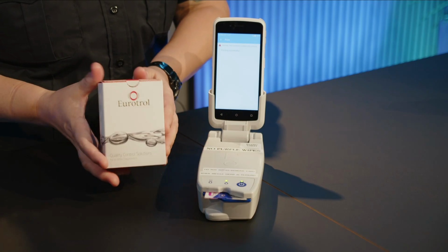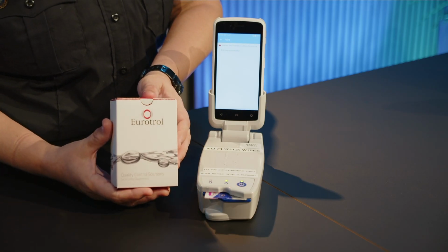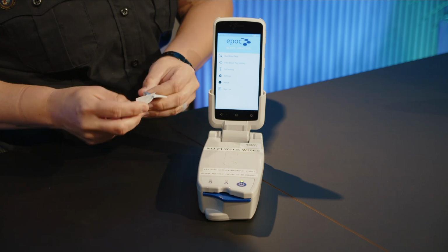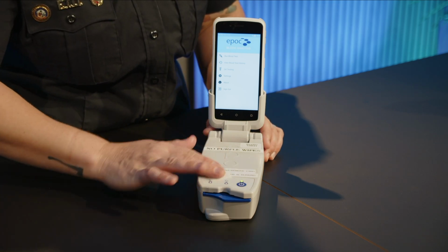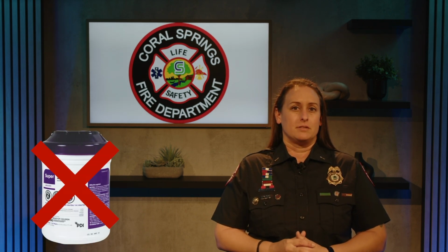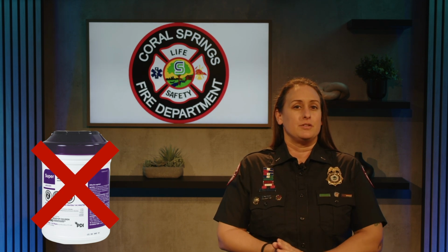To keep the epoc system working properly, regular maintenance is key. The device performs an internal quality control check every time you insert a test card, but we also need to do external quality control using commercial control fluids periodically. When it comes to cleaning, use alcohol wipes or mild detergent. You can also use 10% household bleach solution, diluted 9 parts water to 1 part bleach. Avoid the hospital-grade disinfectant wipes, like the purple ones, as they can erode the device and interfere with sodium readings.